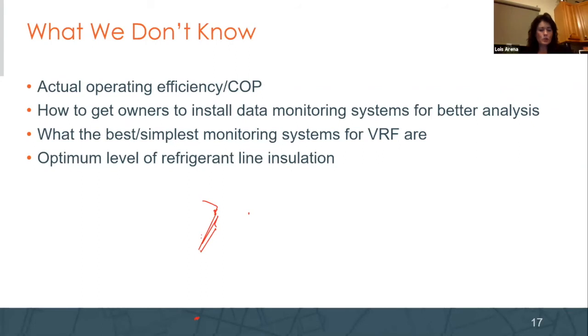So some of the things we still don't know are what the actual operating efficiency or COP of these systems is. I've heard that the manufacturers have these great monitoring systems and can do all this analysis. I haven't seen one in any of our projects. We need to figure out what it is for each manufacturer, what it is they own, what it is we need to see, and make sure in design that we're going to get that, because we don't have enough data points in the system to be able to evaluate. They supposedly can get it for us, but we just can't get it because it hasn't been ordered up front.